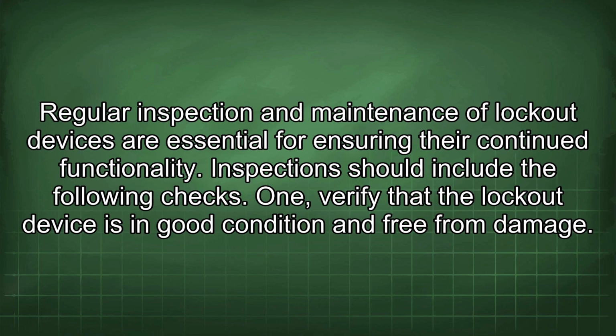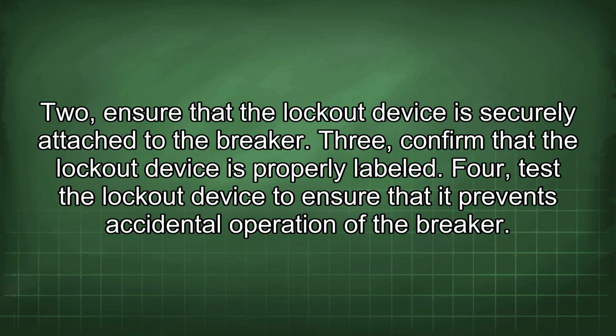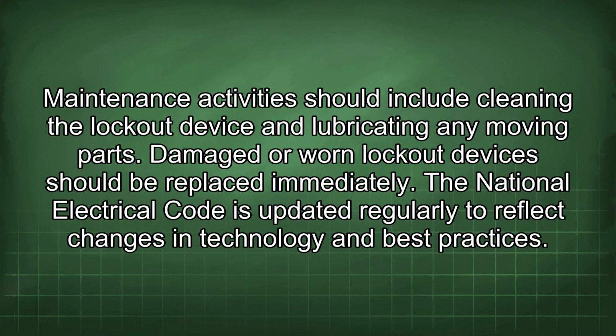Regular inspection and maintenance of lockout devices are essential for ensuring their continued functionality. Inspections should include the following checks. 1. Verify that the lockout device is in good condition and free from damage. 2. Ensure that the lockout device is securely attached to the breaker. 3. Confirm that the lockout device is properly labeled. 4. Test the lockout device to ensure that it prevents accidental operation of the breaker. Maintenance activity should include cleaning the lockout device and lubricating any moving parts. Damaged or worn lockout devices should be replaced immediately.